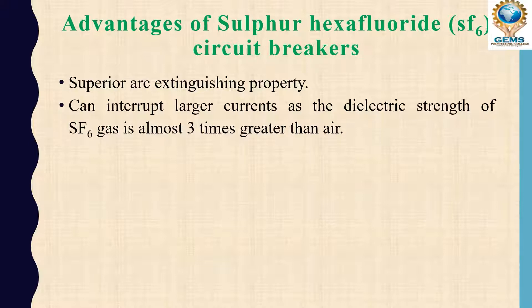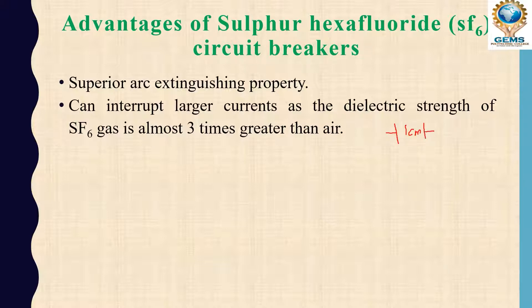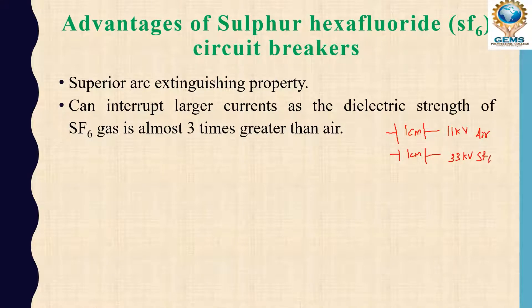It can interrupt large currents as the dielectric strength of SF6 gas is almost three times greater than air. For example, in one centimeter of air, we can hold about 11 kilovolts. But that same one centimeter of SF6 gas can hold 33 kilovolts. This means for the same voltage, SF6 requires much less spacing between conductors compared to air.